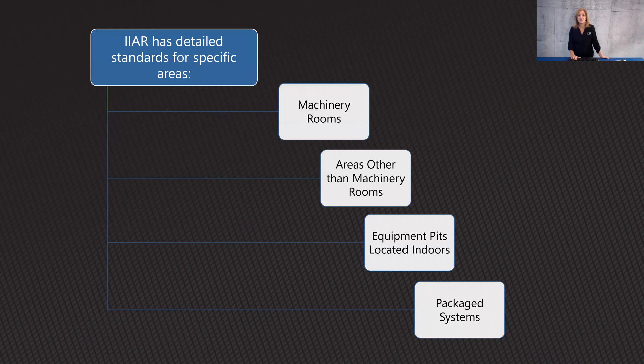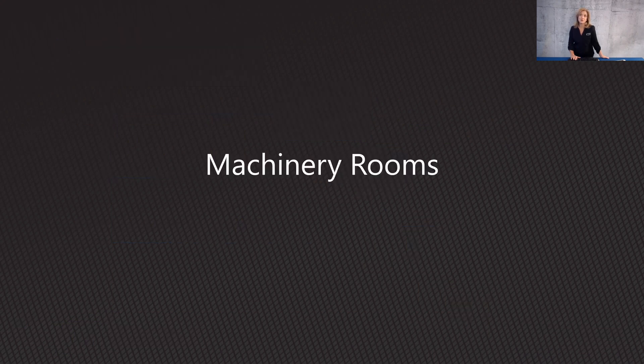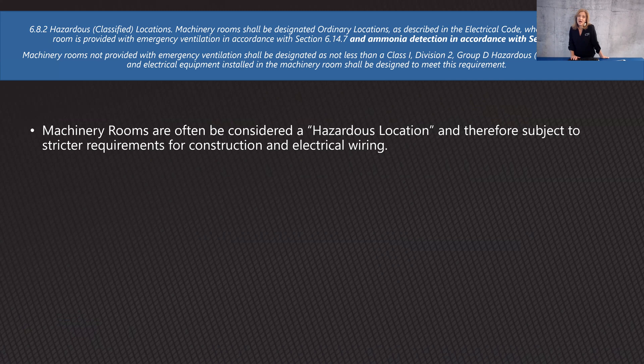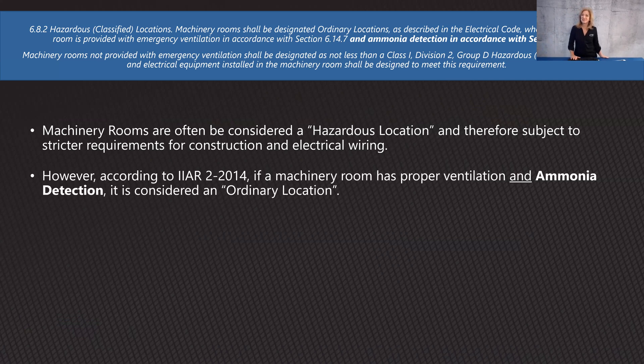IIAR has standards for specific areas: your machinery rooms, areas other than machinery rooms, equipment pits located indoors, and package systems — all with different rules. Machinery rooms have the strictest standards because that's where most of your ammonia is located, covered under section 6.8.2. Your machinery room can be classified as a hazardous location or an ordinary location. You really want ordinary, because hazardous classification involves additional requirements around electrical wiring and construction. To qualify as ordinary, your machinery room must have proper ventilation and ammonia detection.